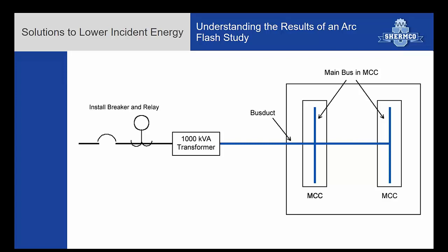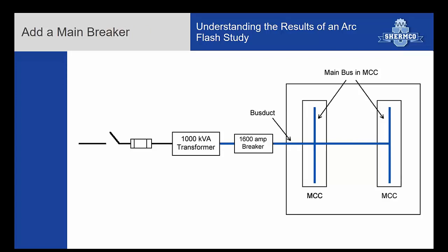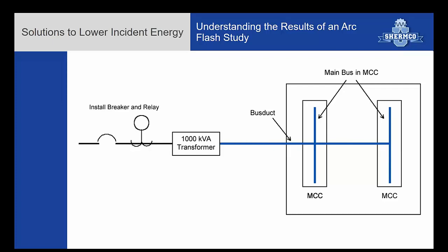We might be able to add one on the primary though. Here, if you notice, we have a fuse switch on the primary. We might be able to remove that fuse switch and install a breaker on the high side and be able to protect on the low side. Fuses have very little selectivity, but if we put a breaker in with a relay, we might be able to lower the incident energy enough.